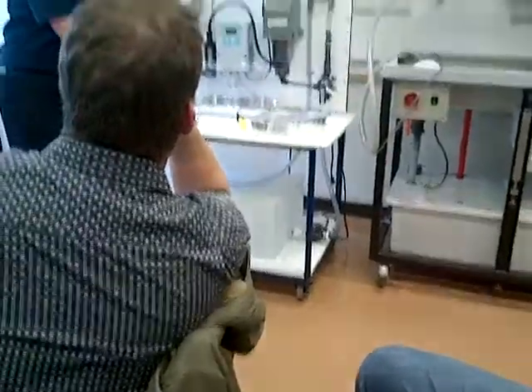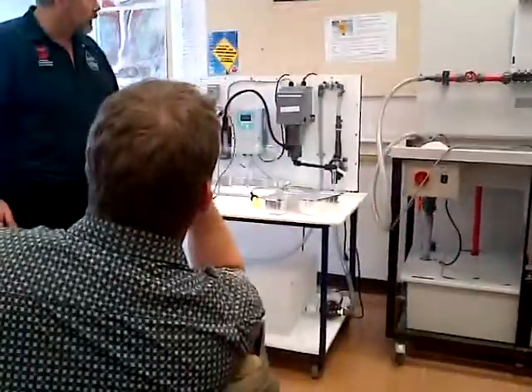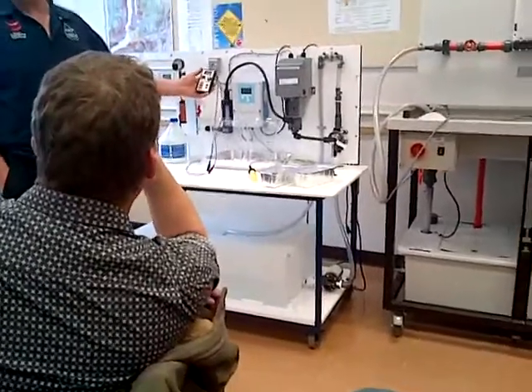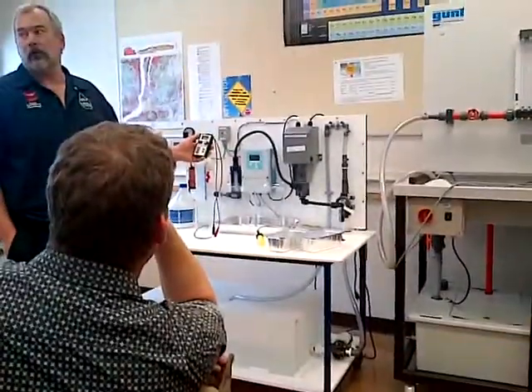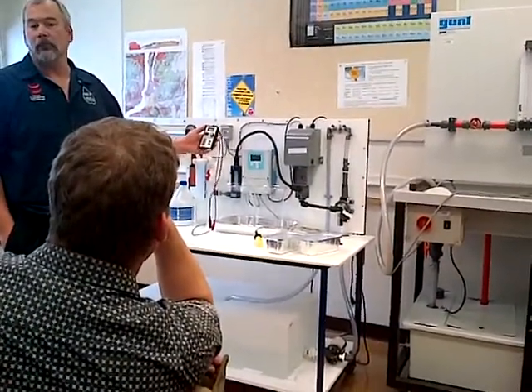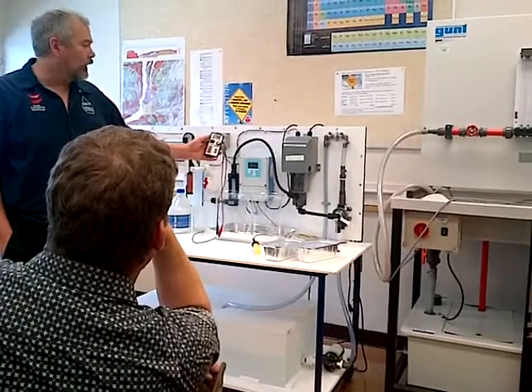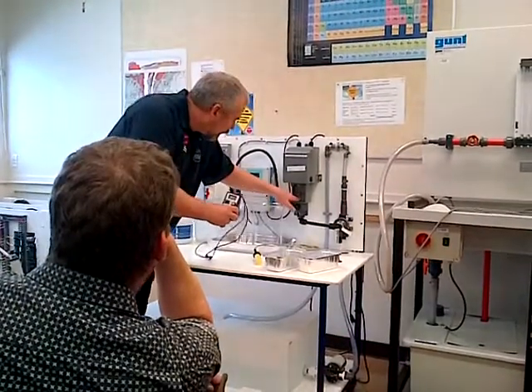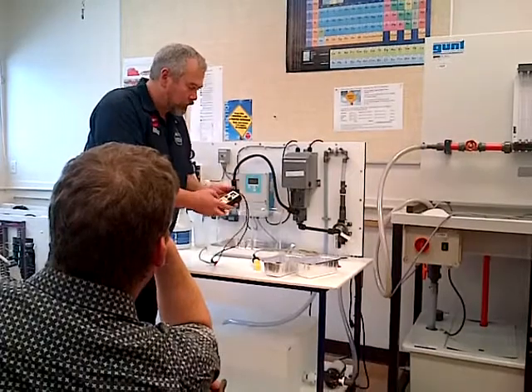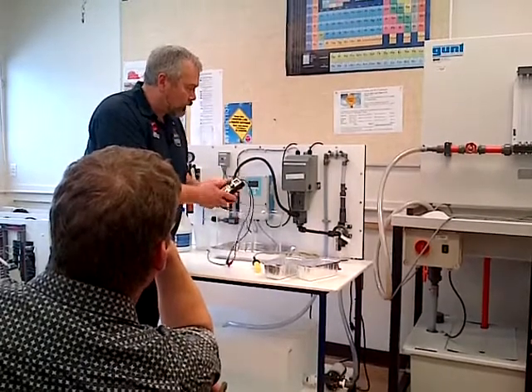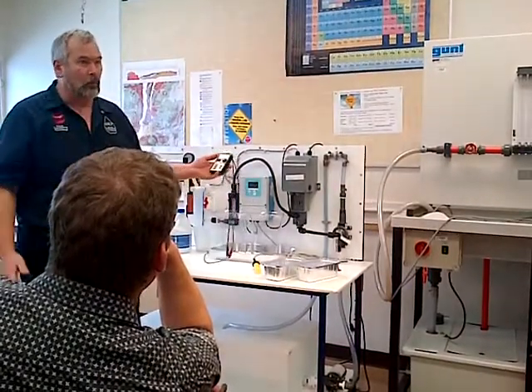So you're going to switch to source and set it to 4 milliamps. 4 milliamps for a 4 to 20 milliamp transmitter. 4 milliamps equals what? Off, 0, yes. And indeed, you should have off or closed. If I bump it up to 20 milliamps, they'll go all the way open.